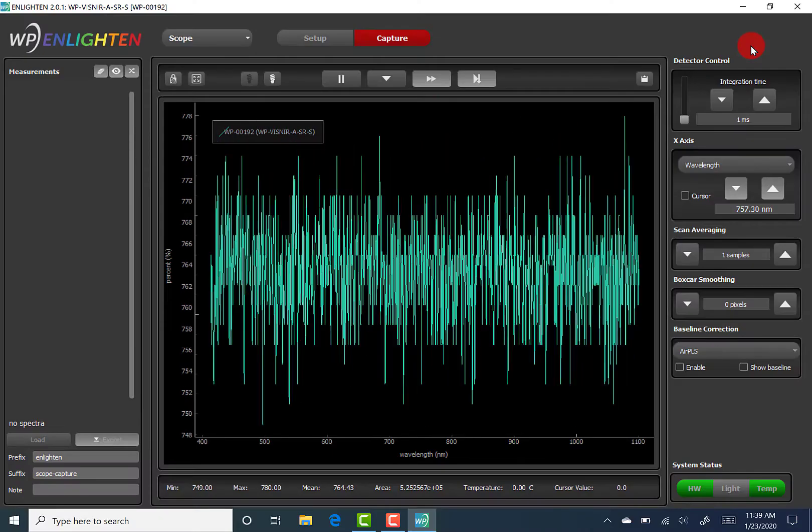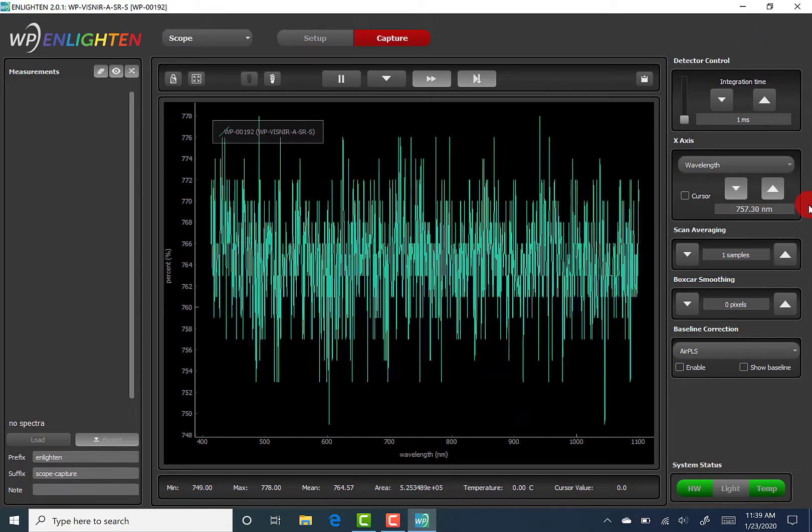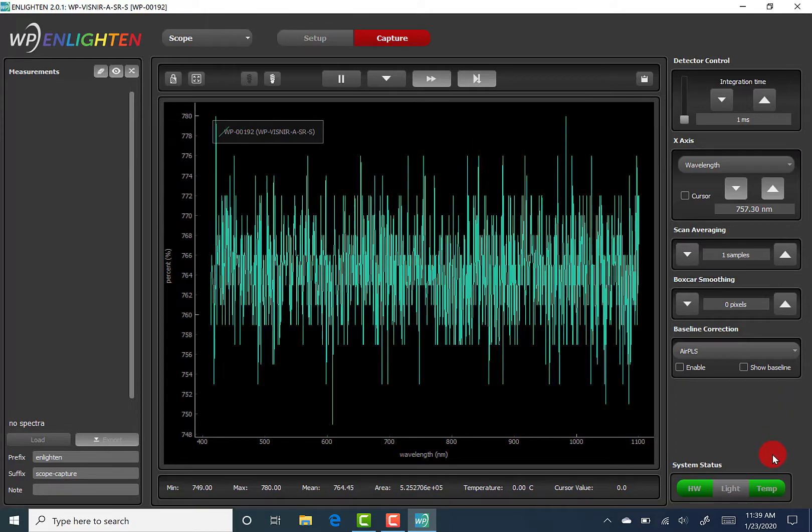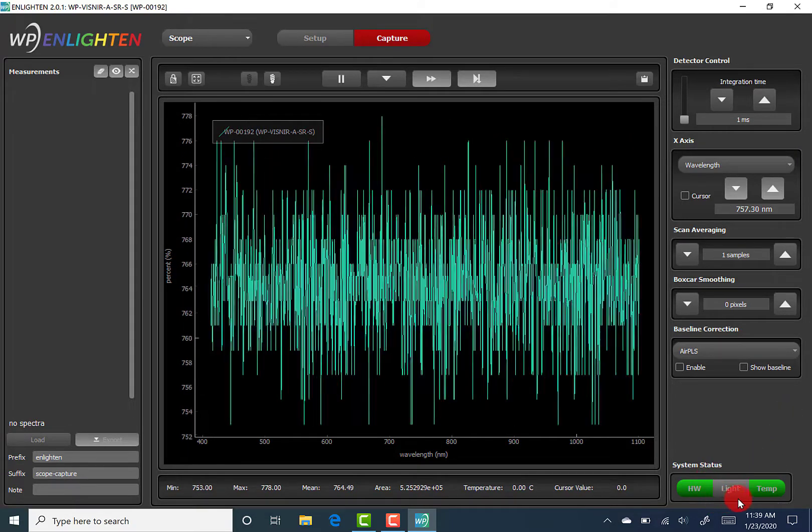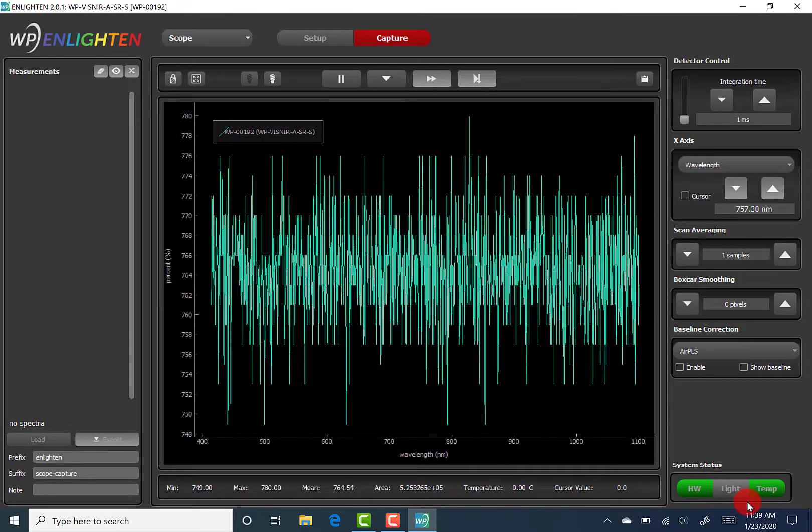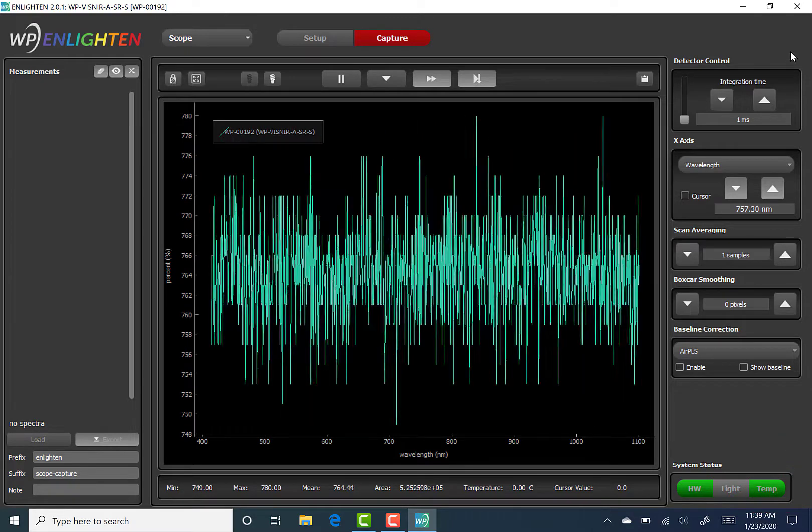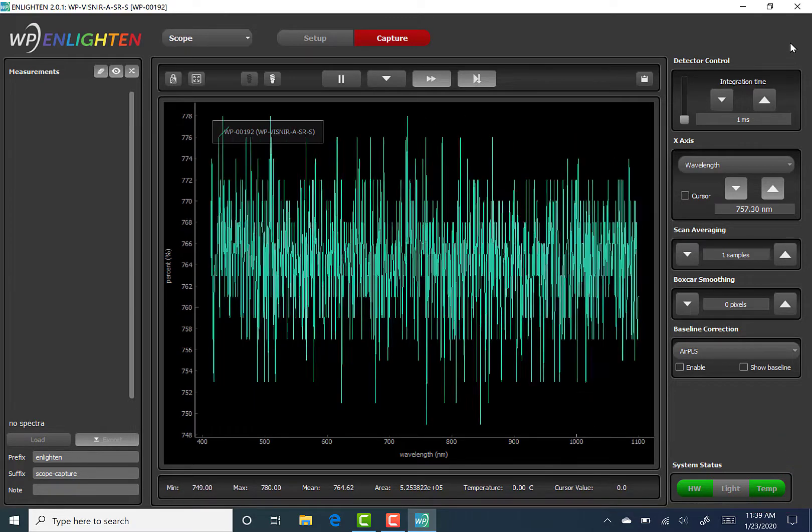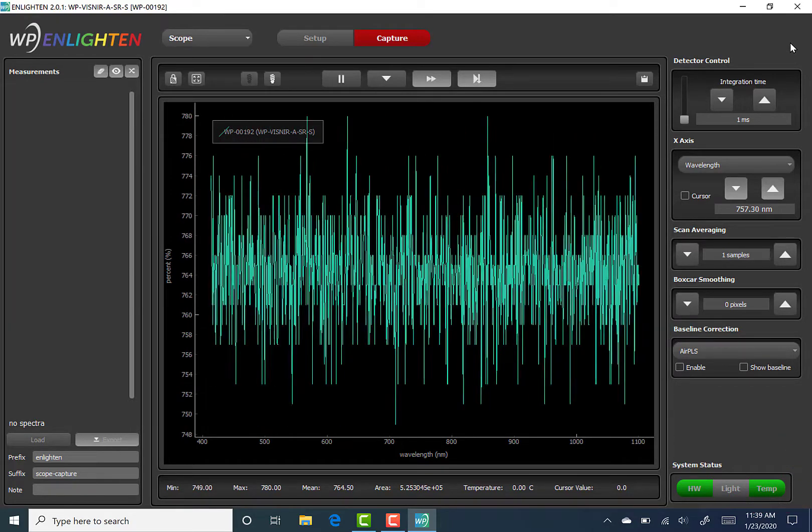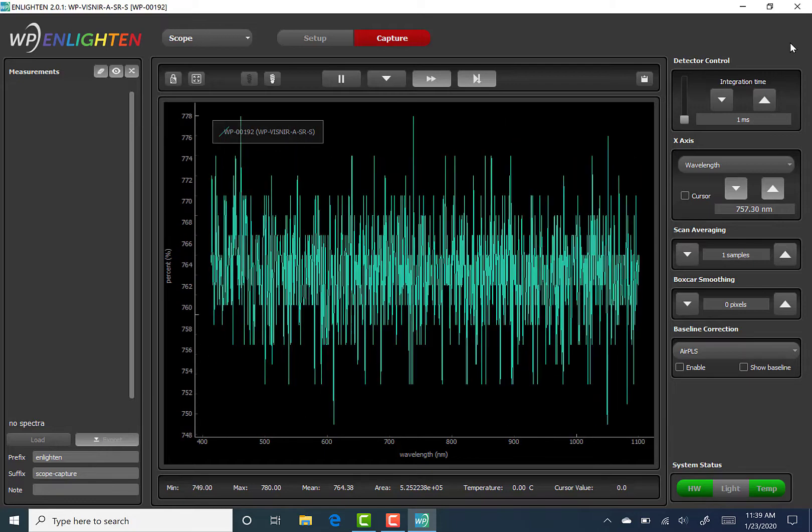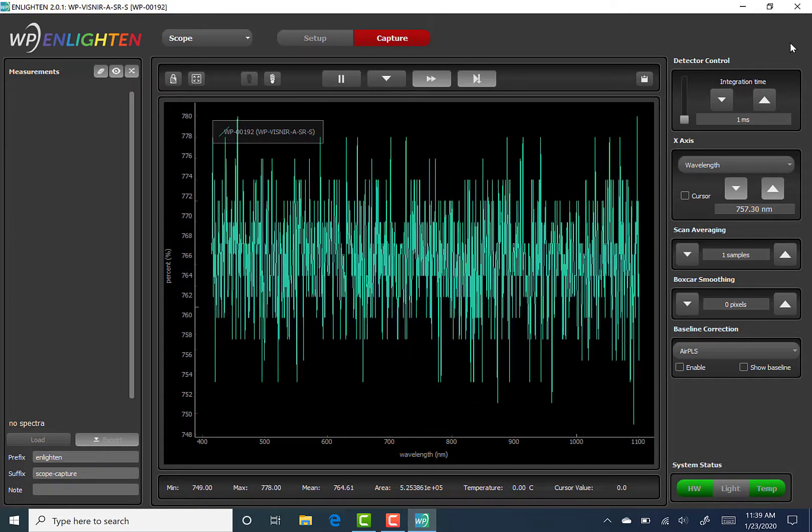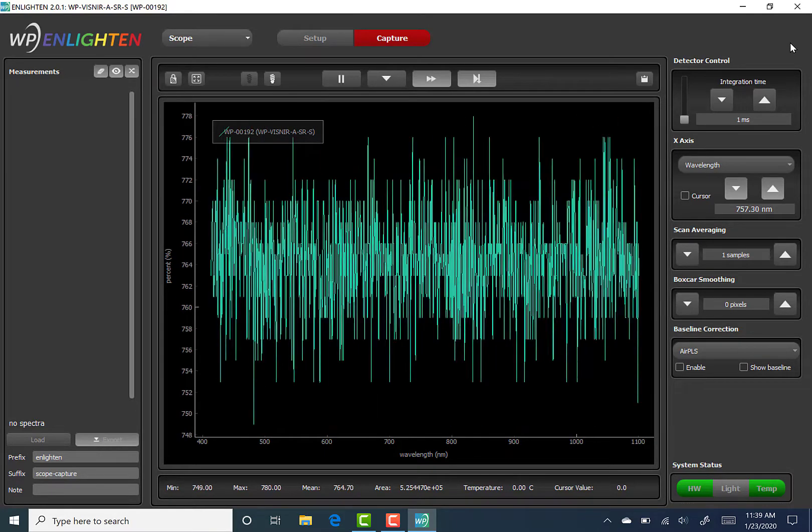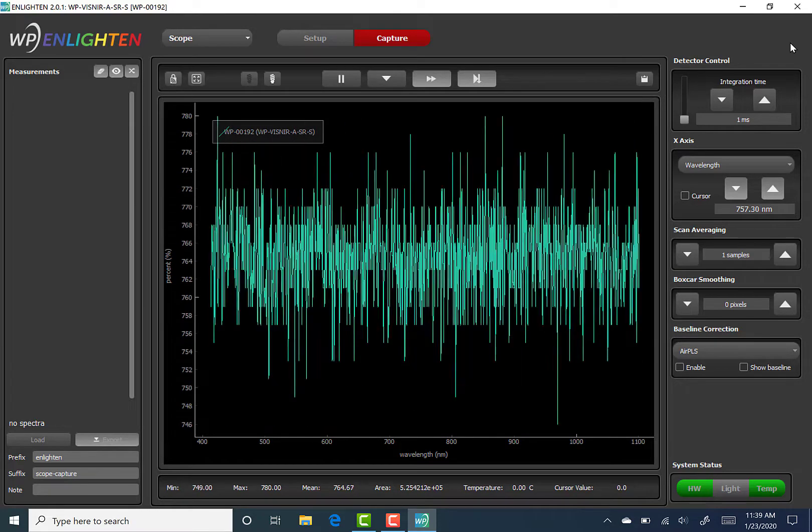Please also note that if your spectrometer does have a laser, the status indicator color for light source will change from green to yellow once it has been enabled by the toggle light source button. Lastly, if the spectrometer contains a laser power calibration, this control may allow the user to switch between setting laser power as a percentage of full power and an absolute value in milliwatts.